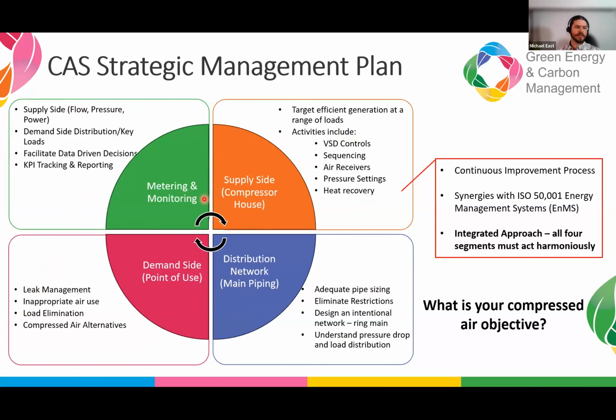But the reality is it comes down to making sure all 4 of these are working in conjunction with each other. For example, the common obvious project is to make sure you've got a VSD controlled compressor, but that's not going to be any good if you've got piping restrictions in your distribution network - maybe multiple compressor rooms where those compressor houses can't see each other clearly through the pressure and piping restrictions. So you've got control conflicts and excess energy being used, and that might also mean your supply pressure is higher than it needs to be, meaning all your demand side applications are using a lot more air than what they realistically need.